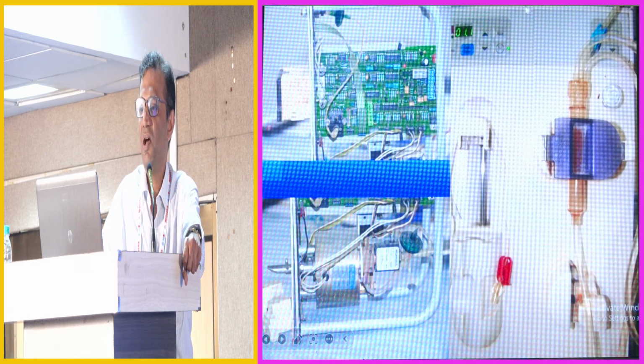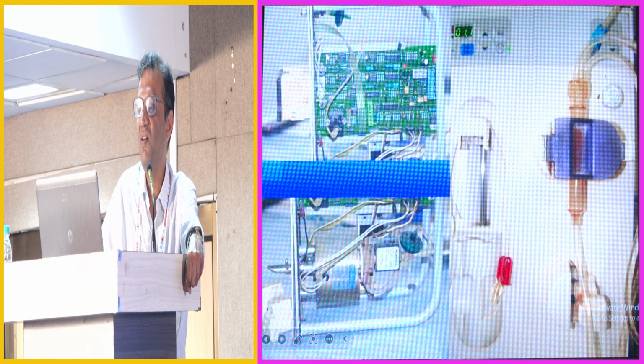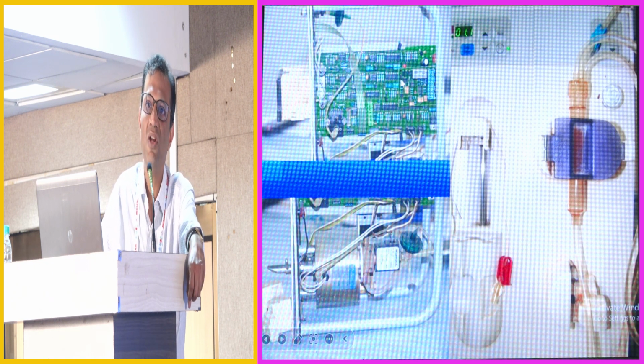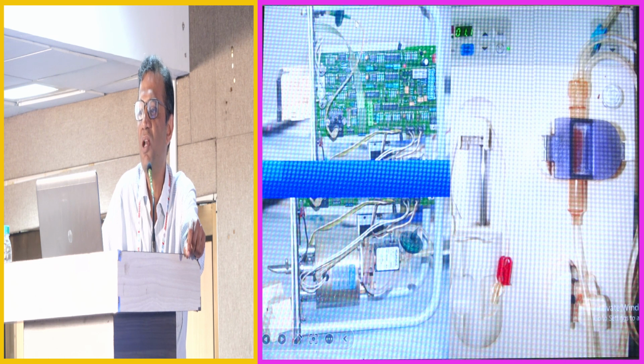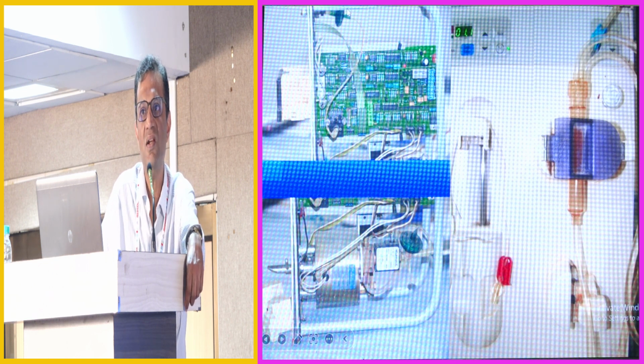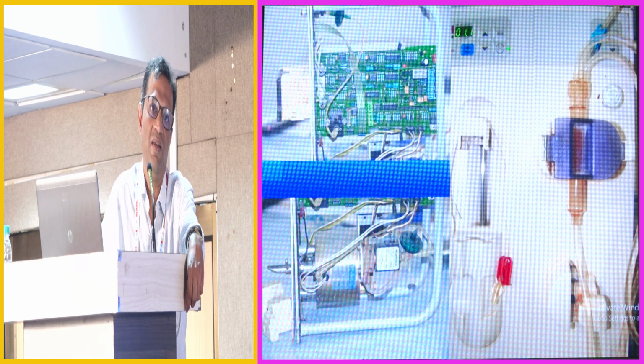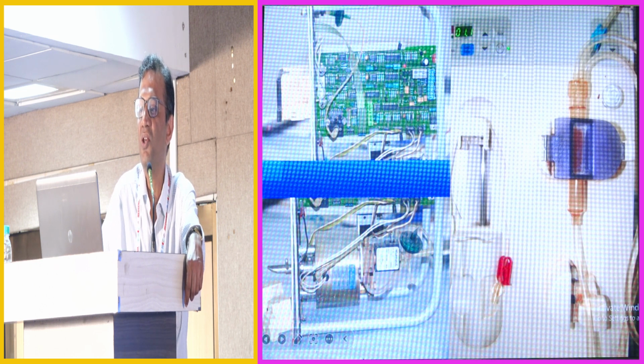line clamp. Now, this is what it looks like from the inside. So this is the venous circuit card. You can see we put a small transducer protector on the outside. There is also a transducer protector on the inside of the venous port which protects this strain gauge sensor over here. If blood were to cross our external transducer protector, this transducer protector would still protect our transducer which is located here, but then we would have to change the internal protector before reusing the machine. And you can see these two ports over here, these are from the air detector. So this is the feedback of the air detector being given to the venous control card, and this is the motor which moves the line clamp lever.